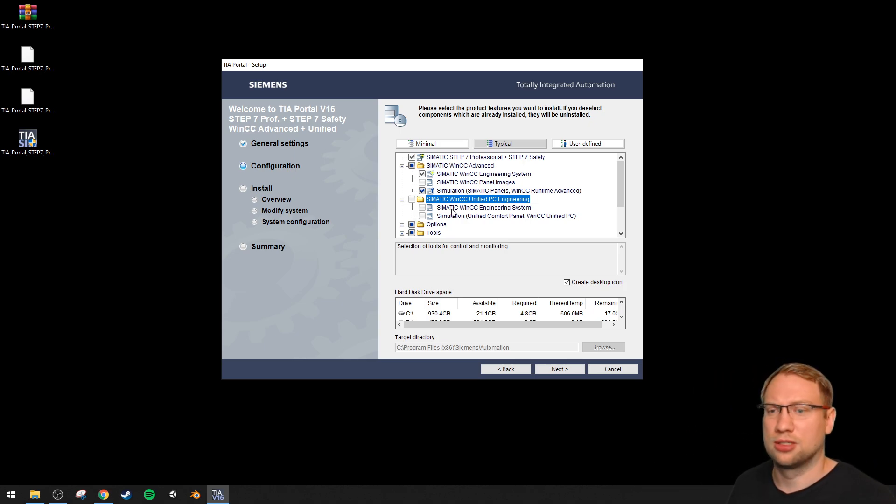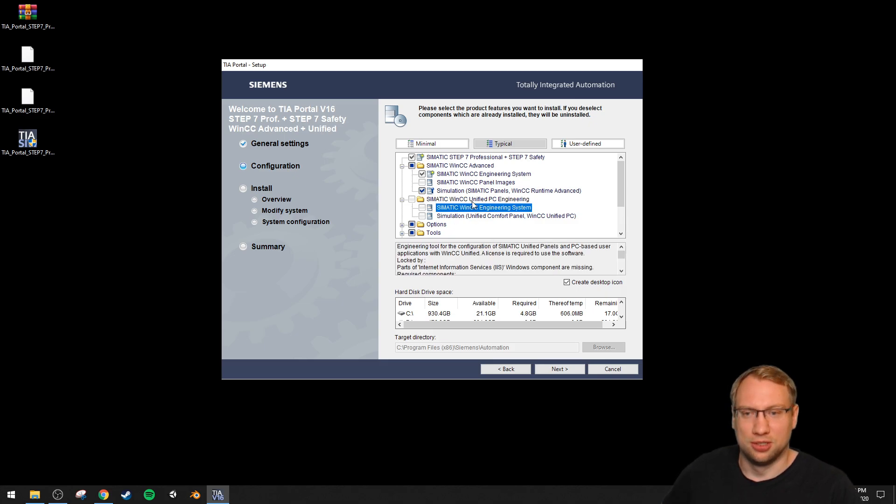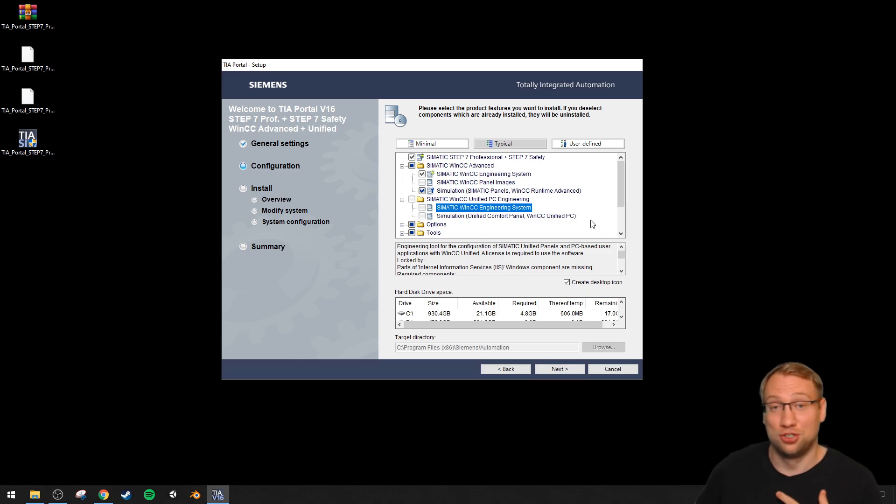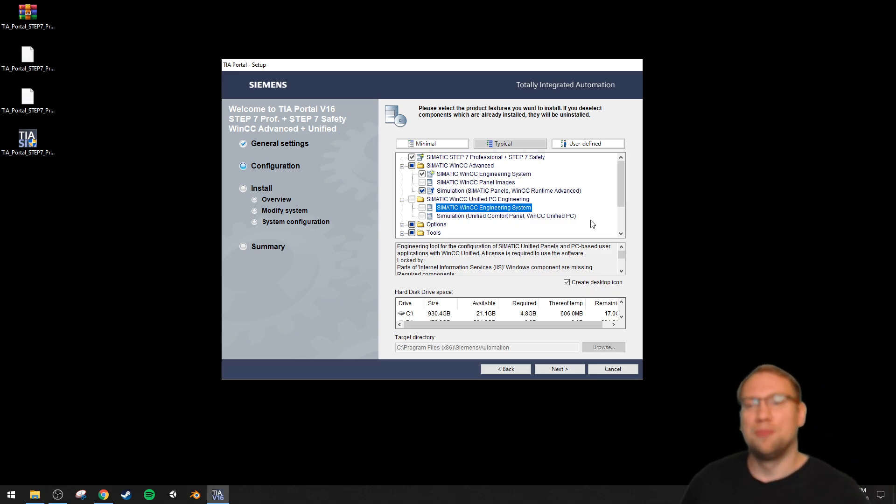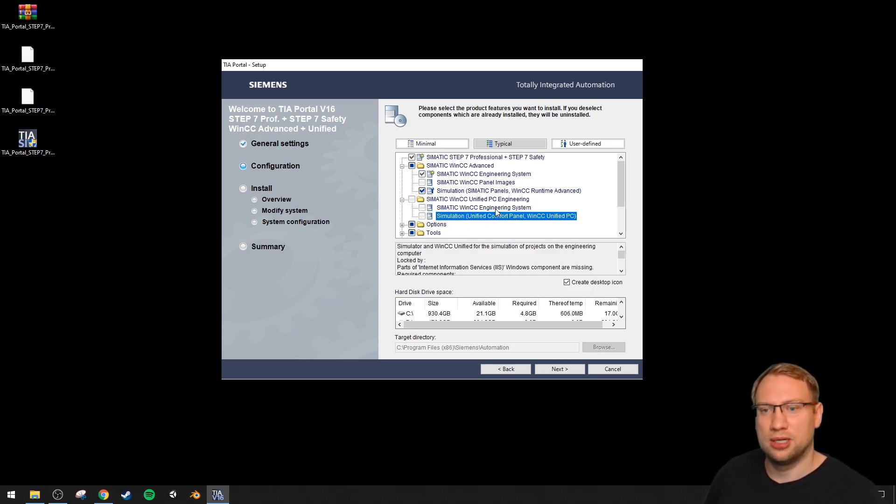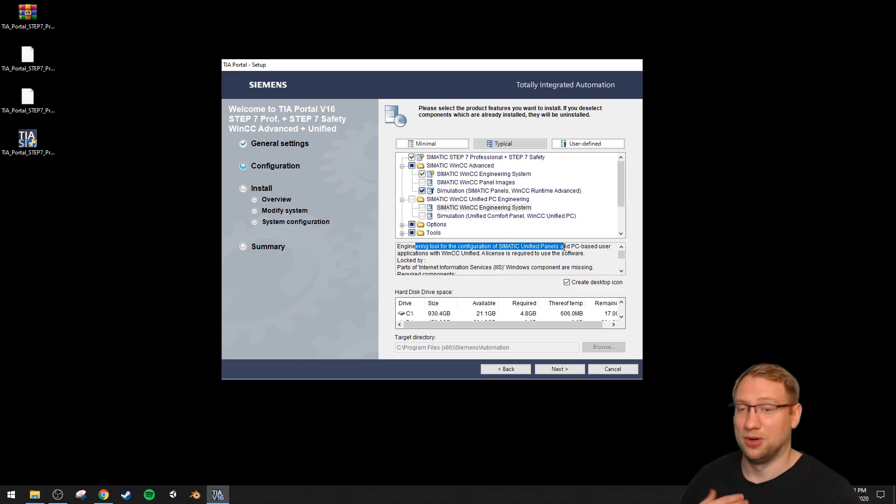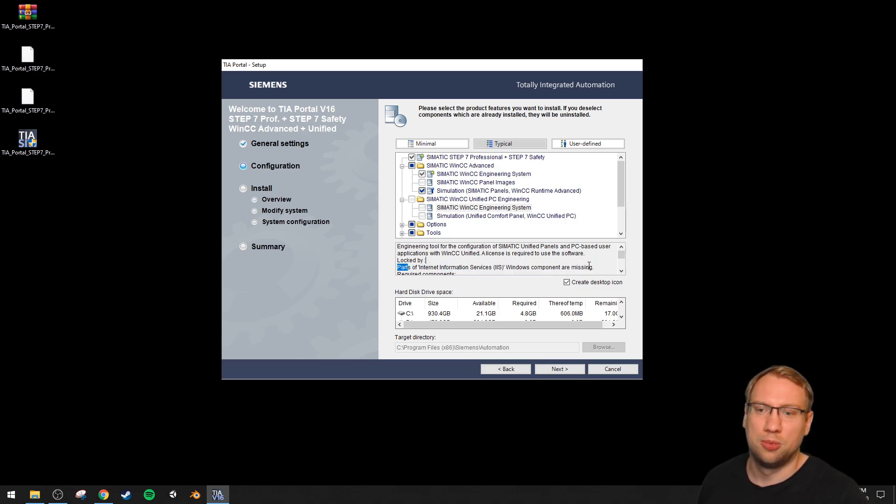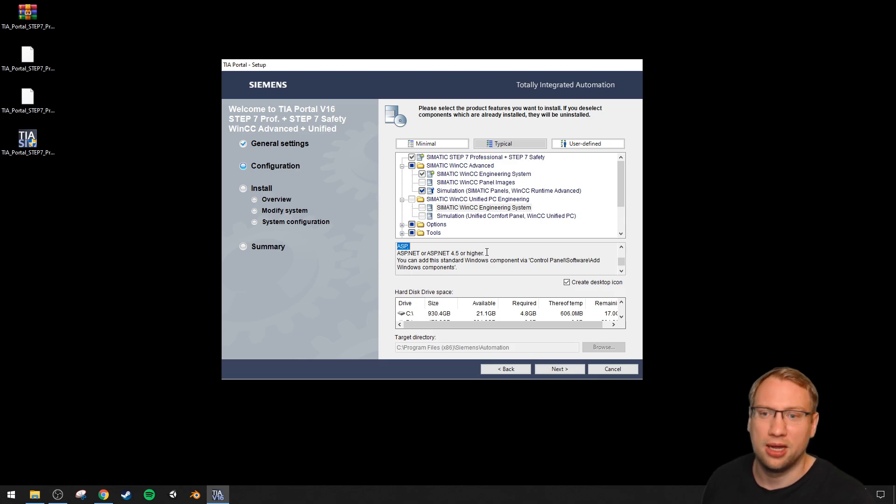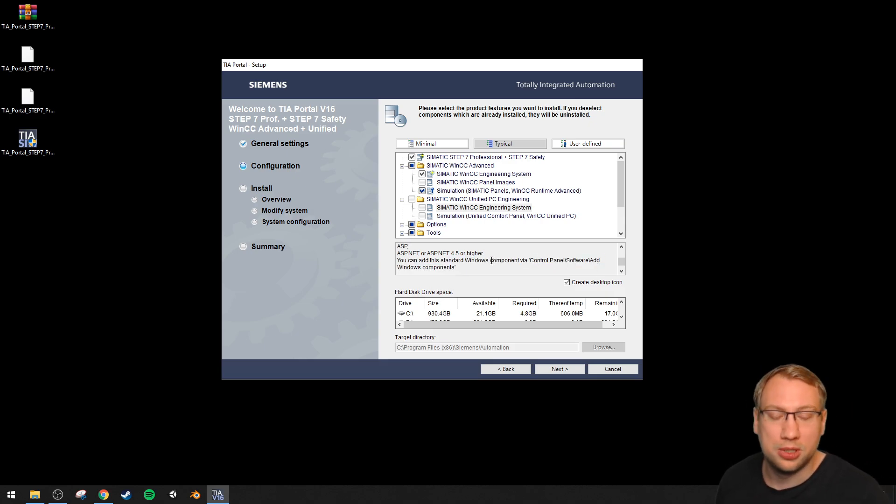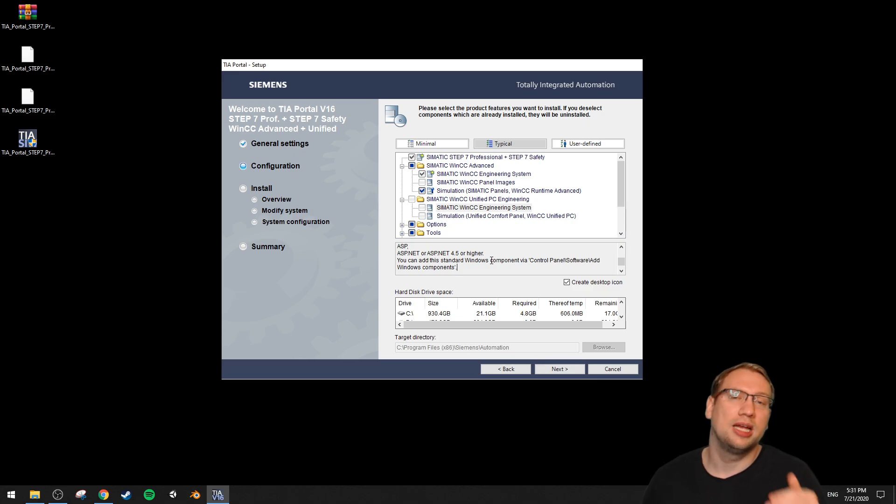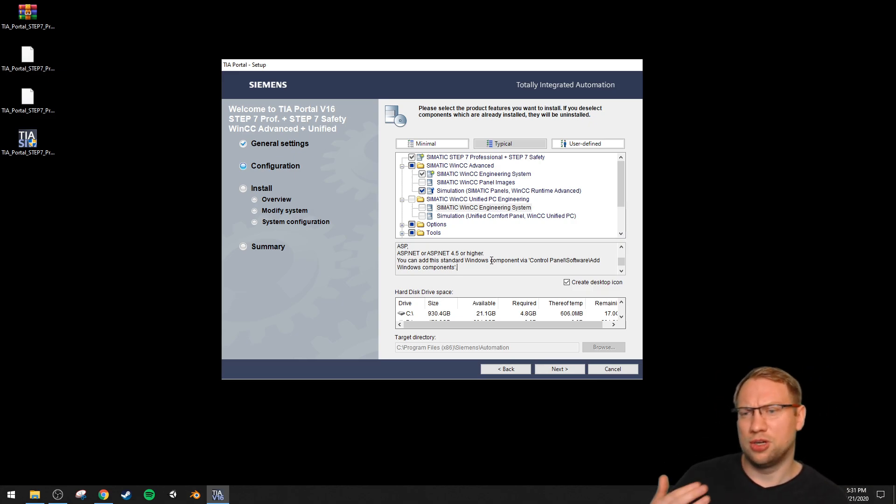To be able to turn these two on - the WinCC Engineering and the simulation for Unified - which I need to work with WinCC Unified, it actually tells you what to do. If I select any of these, it tells me it's the engineering tool for configuration of WinCC Unified panels. Blocked by parts of Internet Information Service. Windows components are missing: required components Static Content, ASP, ASP.NET, ASP.NET 4.5 or higher. You can activate those. It tells me Control Panel, Software, Add Windows Components. So we can just add them - they are already in Windows, they're just not installed, which is very strange.